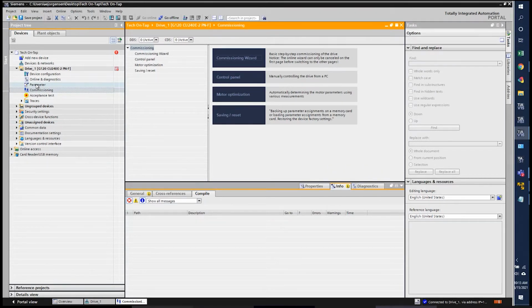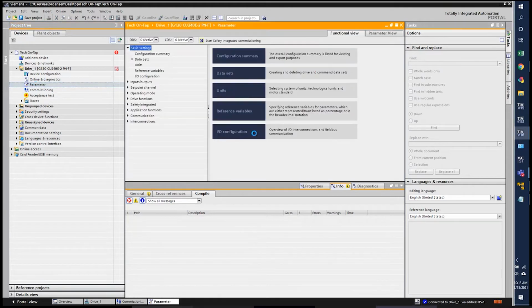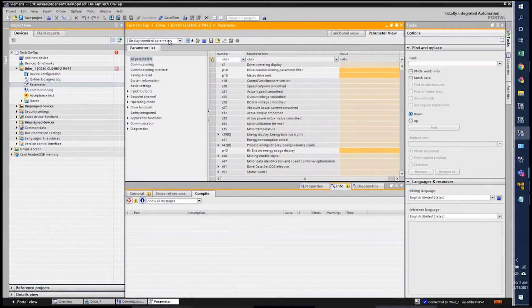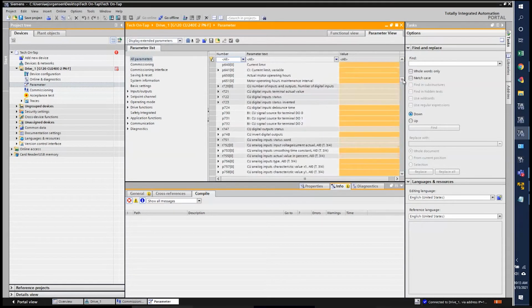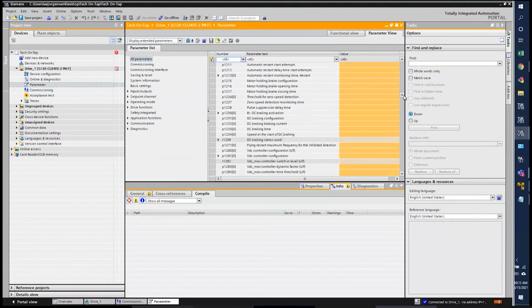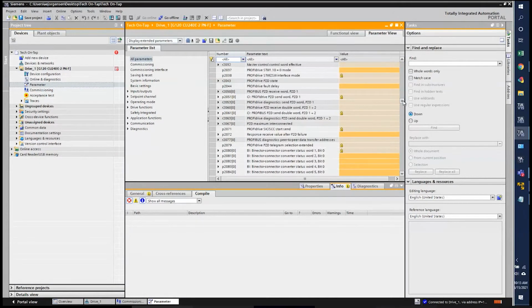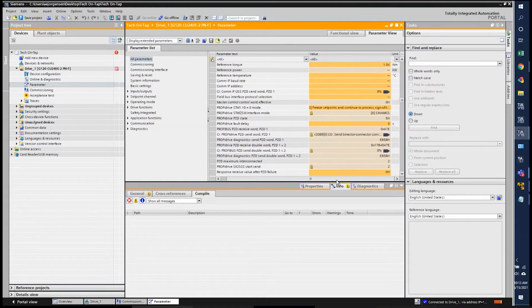And by default, when you select mode 7 for set point over field bus, the drive is going to default to Profinet because it's a Siemens drive. So we need to go pick Ethernet IP. It's parameter 2030. It's right here.